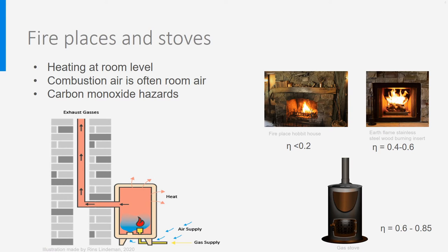There are also systems with an extra pipe so that air is taken from outdoors. In all cases, special attention should be paid to emissions of carbon monoxide, which is an extremely lethal gas arising from incomplete combustion. This is even worse with coal, for which incomplete combustion is more likely and which also emits a lot of particulate matter harmful for human health. CO sensors should be placed in any case.